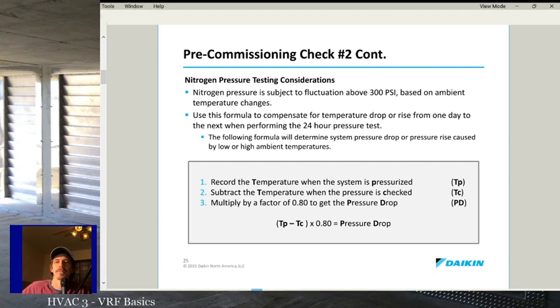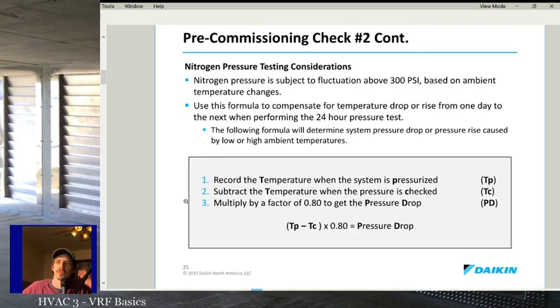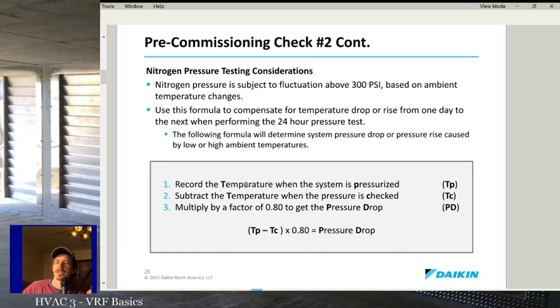Anyway, a lot of people say nitrogen does not change pressure with temperature. That is a lie. Every single gas changes pressure with temperature, no matter what you do. Some things will be more or less affected by temperature changes, or more or less noticeable. When you put air on a pressure test, it's more noticeable because you have a lot of different components in there. You have nitrogen, oxygen, water vapor, and all of these things react differently to the temperature change. But any gas changes pressure with temperature. It is the gas law, okay?